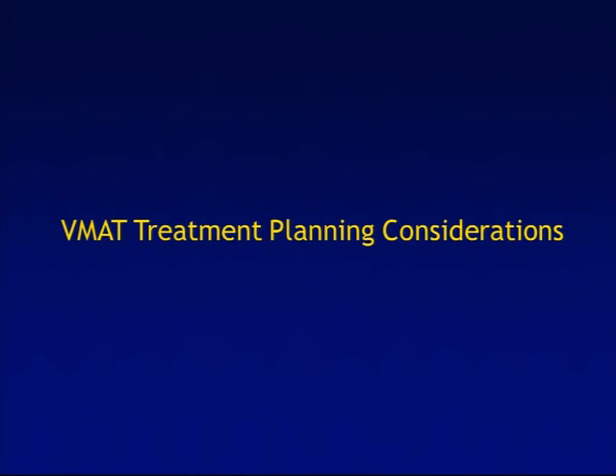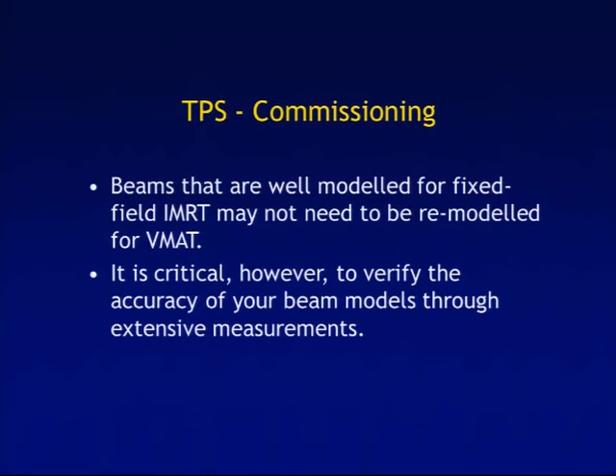Regarding treatment planning considerations for VMAT: ideally, beams that are well-modeled for fixed-field IMRT may not need to be remodeled for VMAT. It's critical, however, to verify the accuracy of your beam models through extensive measurements. Hopefully if things are well-modeled, you don't need to go through a remodeling process, but you have to test and verify that.